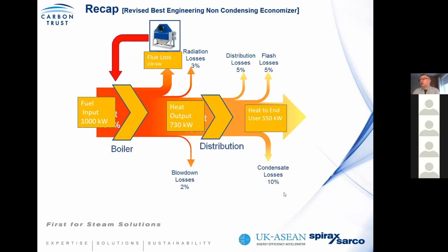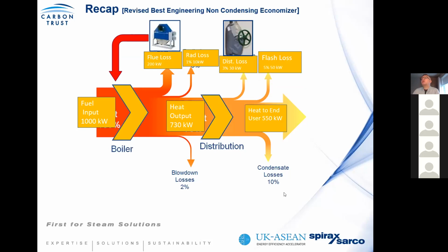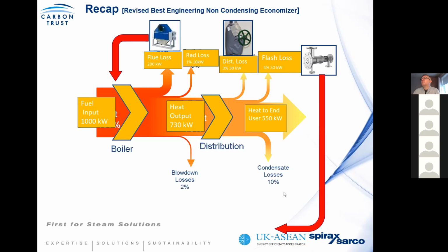Whether a condensing economizer makes sense, but again, there are limitations on the need for a condensing medium below the dew point temperature of the fuel. There are limitations with certain fuel types, biomass boilers, for example. Radiation losses, again, we should be looking at insulation. Distribution losses, looking at insulating those exposed components. The flash losses, look at the recoverable technology, recover that flash energy back into the system.